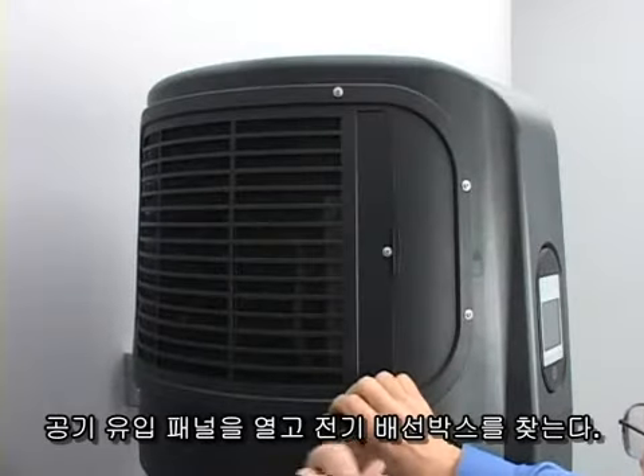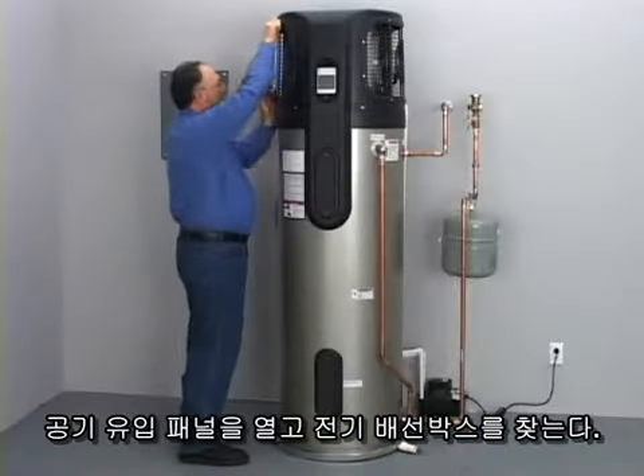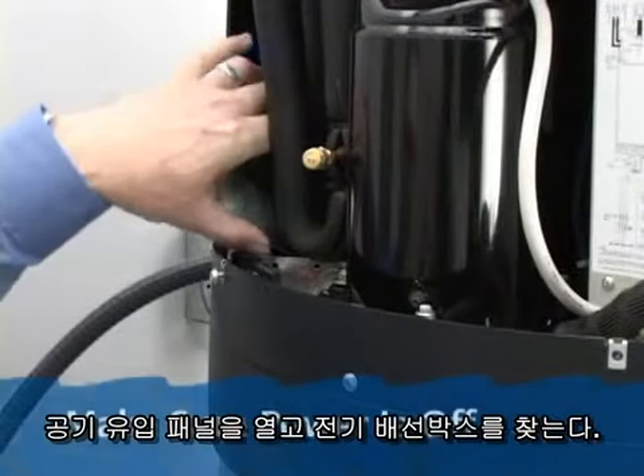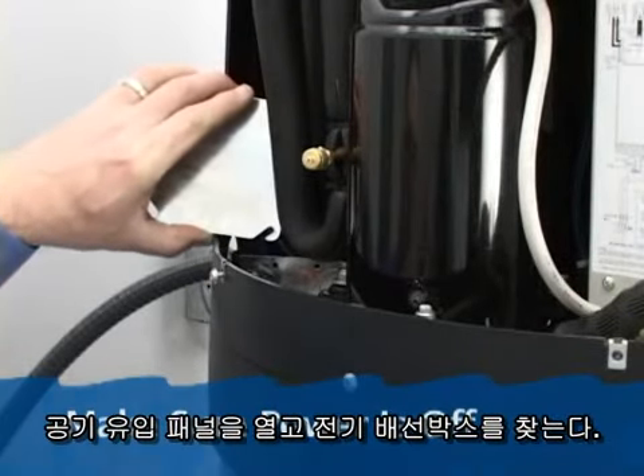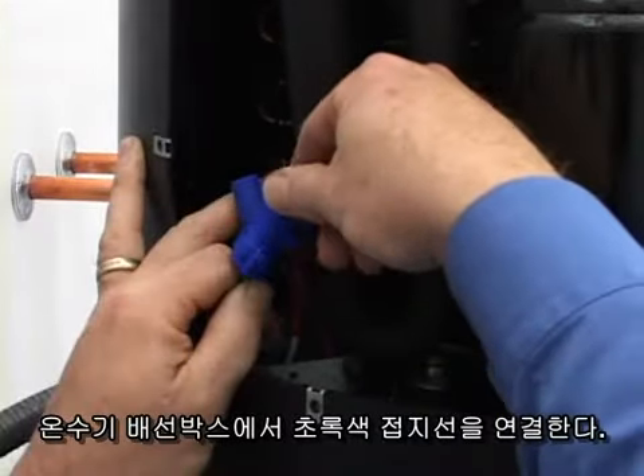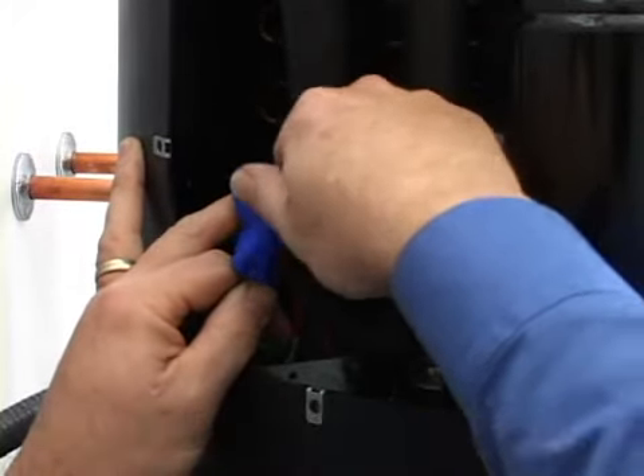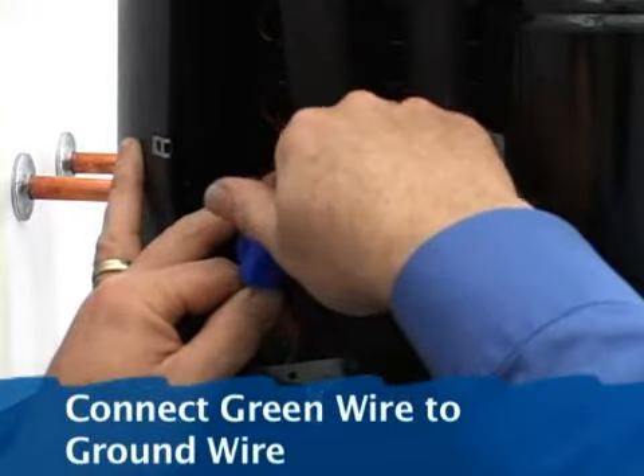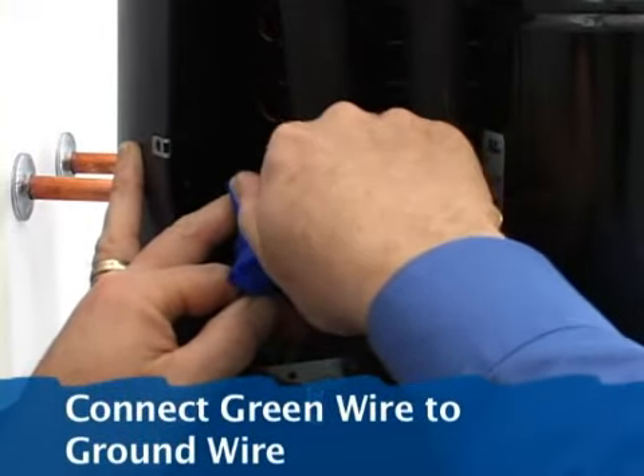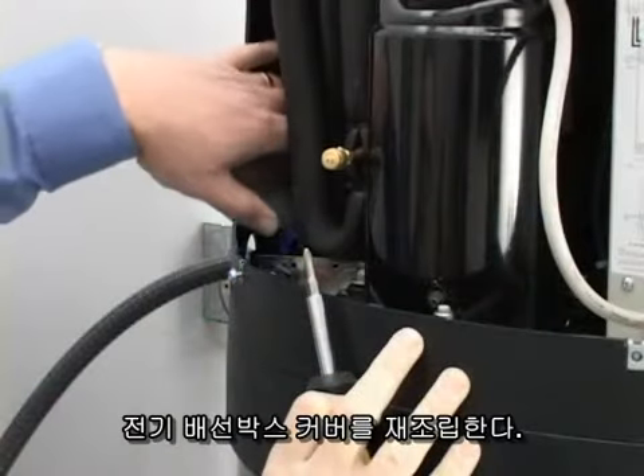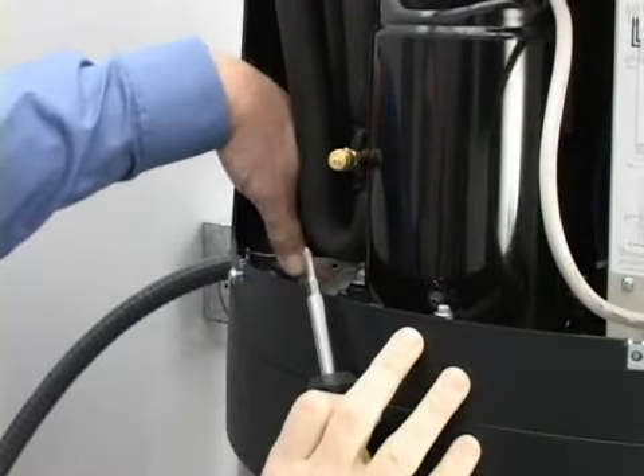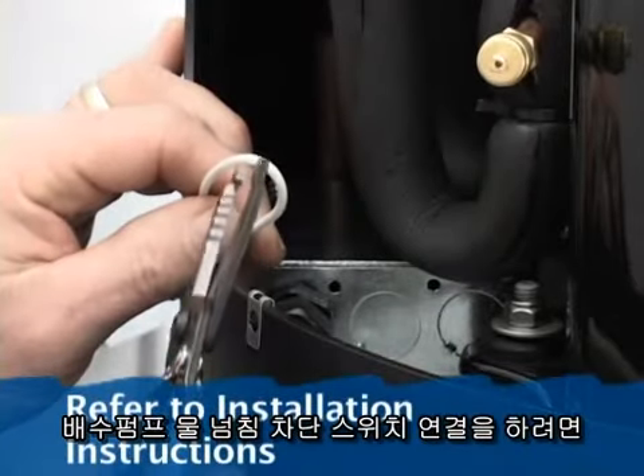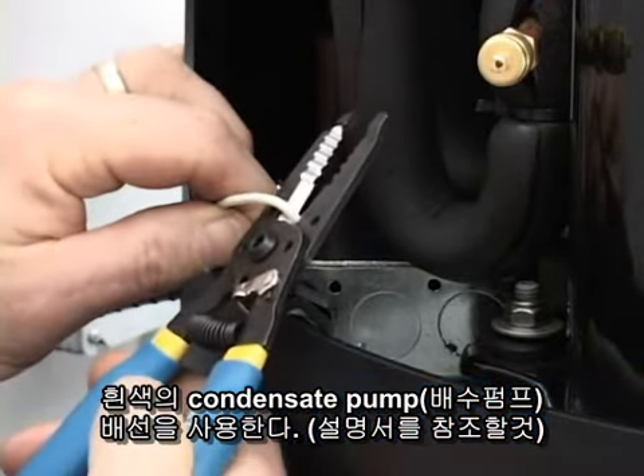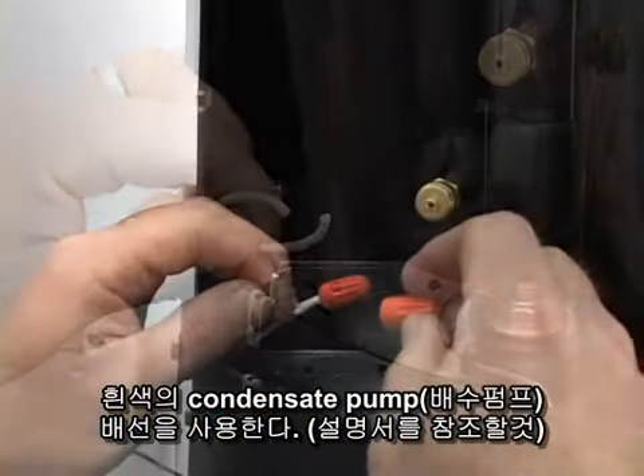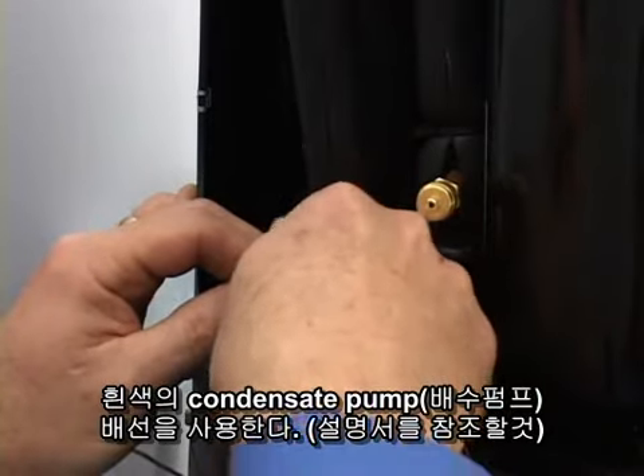Remove the louvered access panel on the left side of the water heater. Remove the cover on the electrical junction box. Install the power wires according to local codes. Make sure that your home's green or copper ground wire is connected to the unit's green ground wire. Replace the cover on the electrical junction box. If you are using a condensate pump, refer to the installation instructions. A control wire can be connected to the condensate pump to shut off the heat pump if the condensate pump fails.